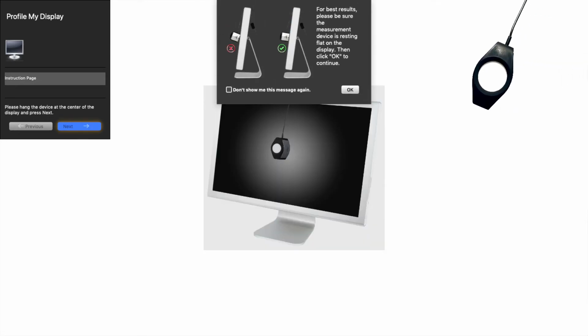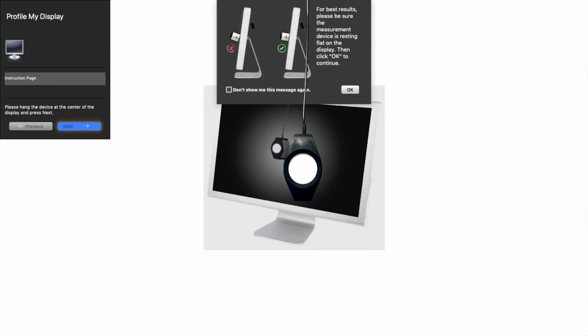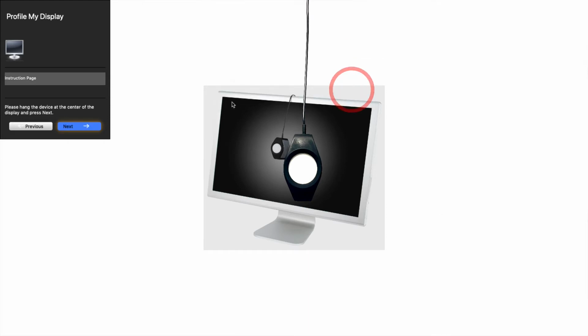If your i1 device cover is in the wrong position, it shows you how to change that right on the screen. Placing the device on the monitor is critical. Tipping the monitor back helps keep it in position. The weight on the cord is also adjustable. Just squeeze the weight and slide it on the cord. The device must lay perfectly flat on the screen. The weight on the cord helps keep it balanced. Once everything is in the correct position, click Next.